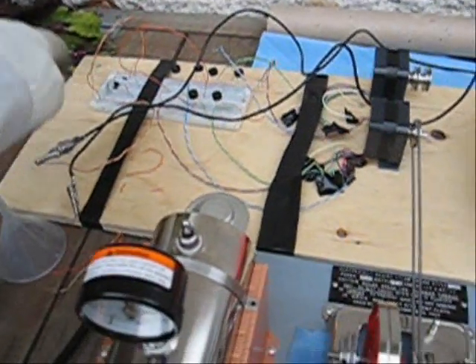So what I've done here is basically the same as the first step, except I have decoupled the center tap. So I have one bridge between these two, one bridge between these two, one between these two, and one between these two. And they all feed to a common DC output bus.